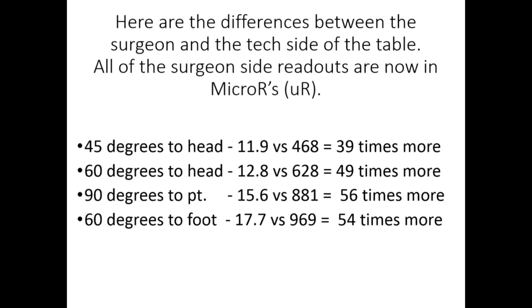At 60 degrees to the foot: tech side 17.7, surgeon side 969 — surgeon side getting 54 times more radiation.